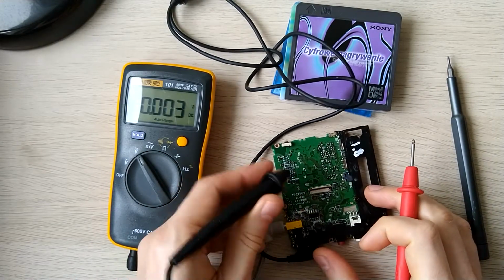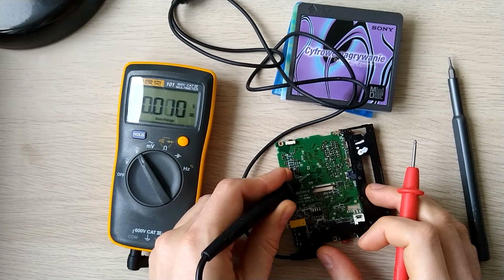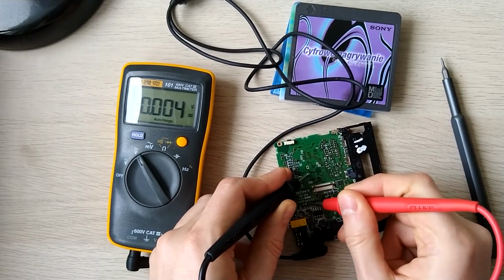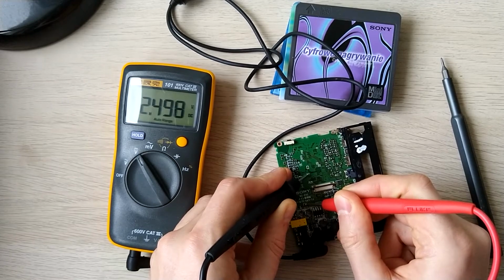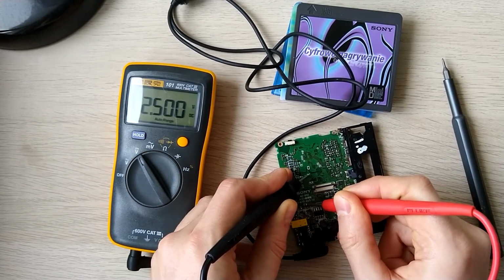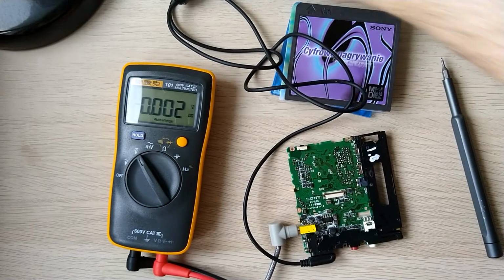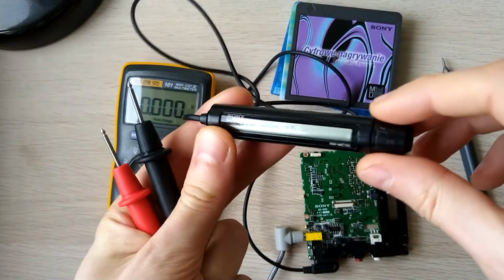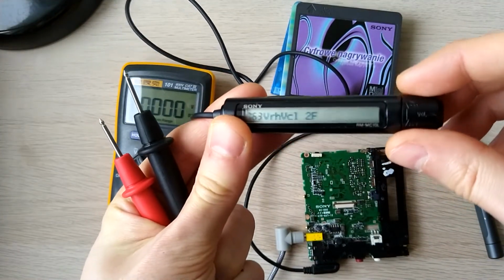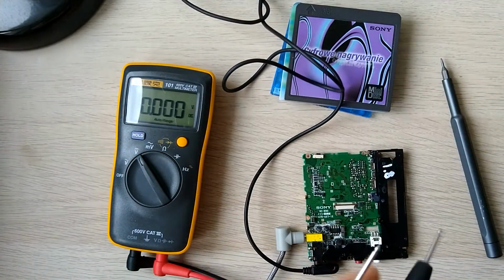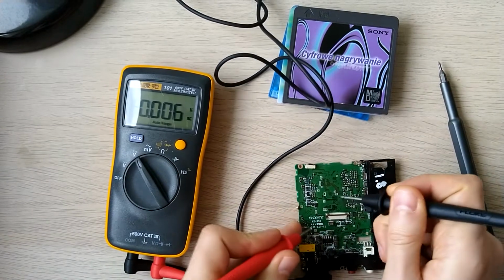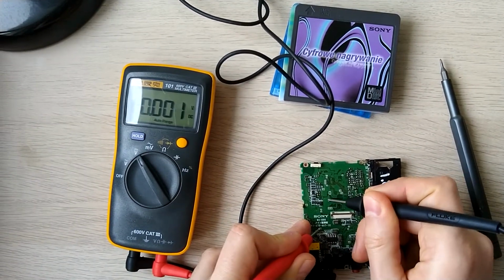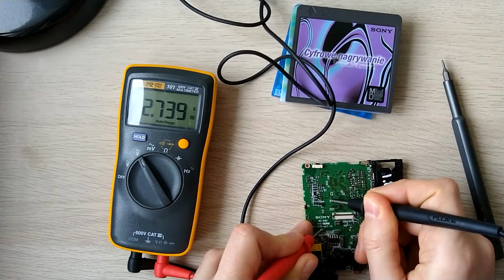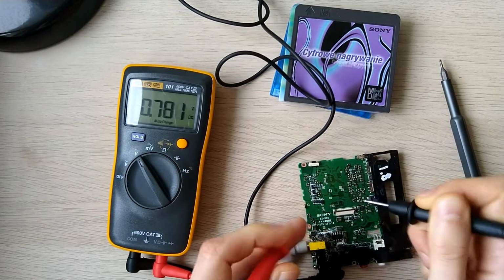So the ground on this device is here, and the test point 915 is here, and this is supposed to be 2.5 volt, which is exactly right on mark, so no adjustment is necessary. Then we move on to the next item, which is 763, then 764, 765. So for example, 765, we are supposed to see 2.75 between those 2 points. And it's 2.74, which is within range, so again no adjustment is necessary.